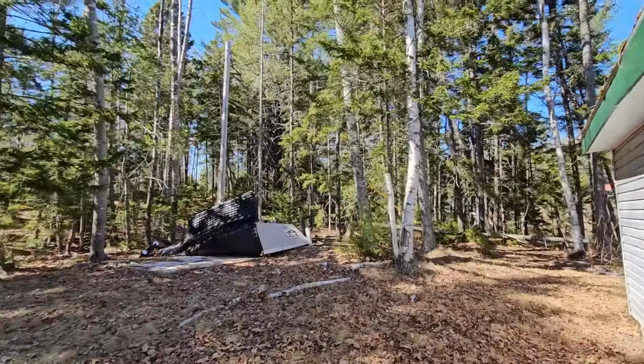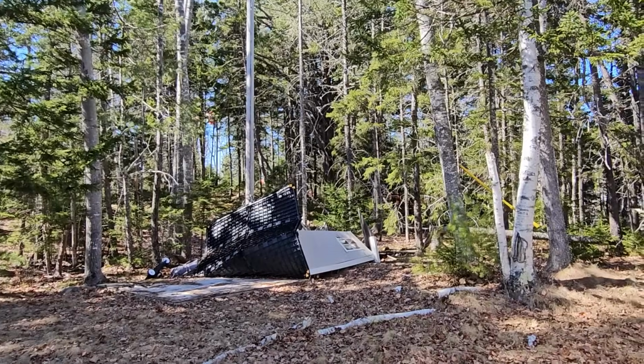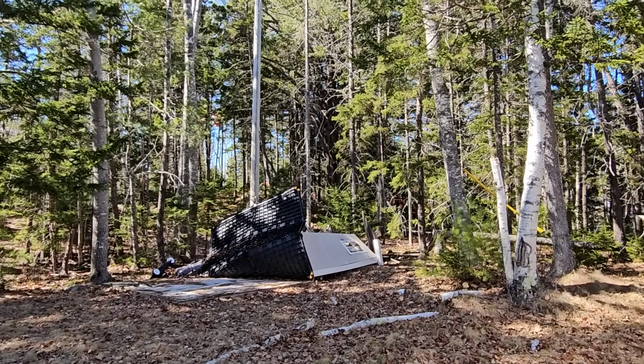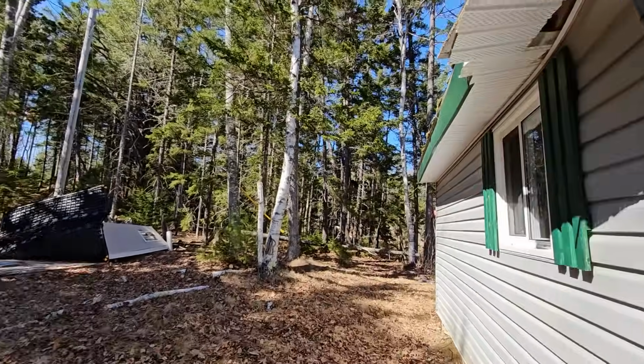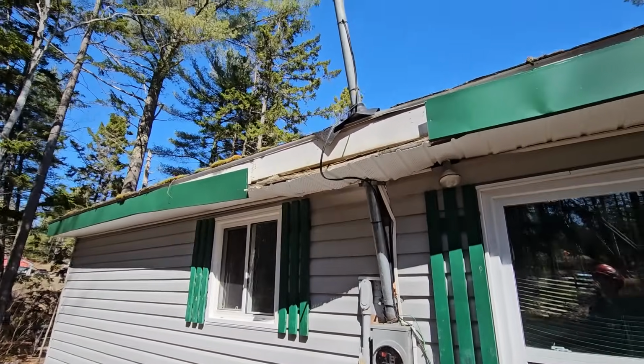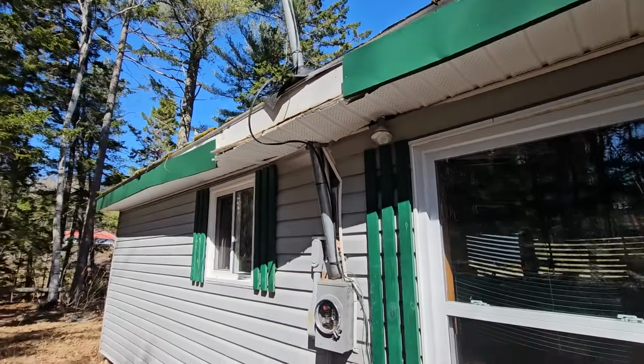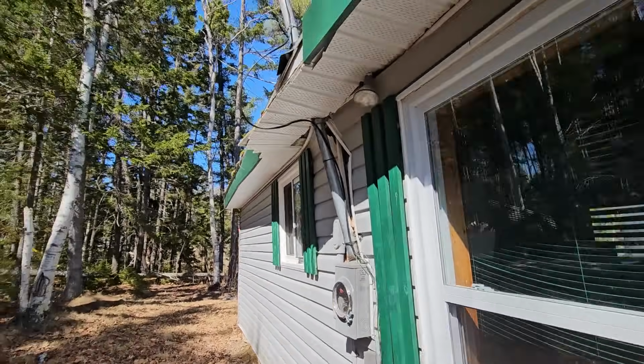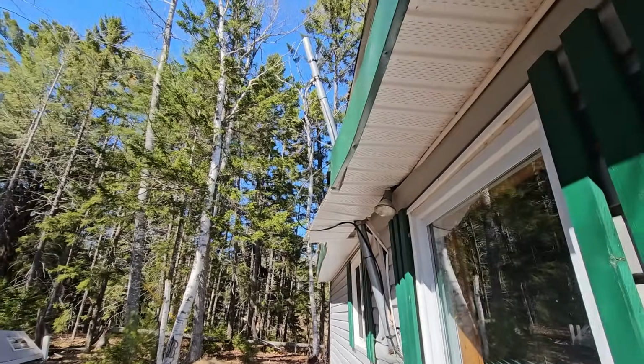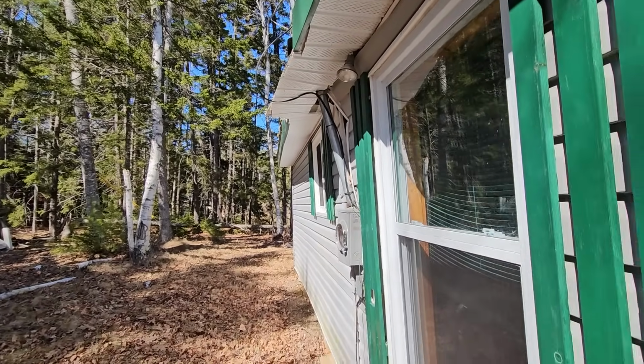You see all the damage, at least 100 meters away. Get all the wire back up in the air, poles are all good. But it's not uncommon to find damage further down the line like that. That's why it's real important to go over the entire work site. If that still had a loop on it, we would have to cut that off. Homeowner would have to get an electrician, make repairs to his mast before we could re-energize that.